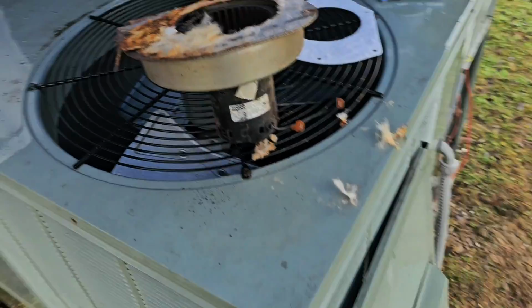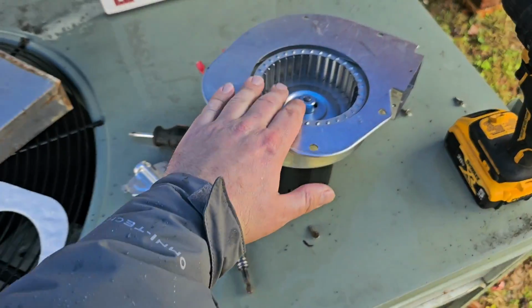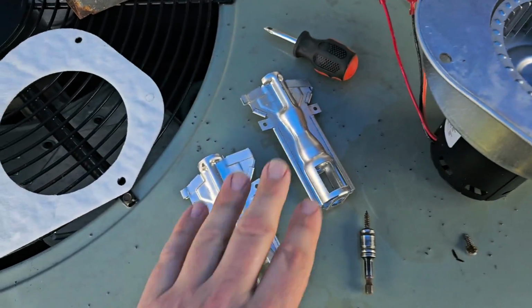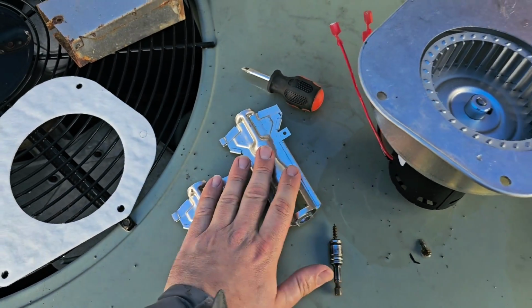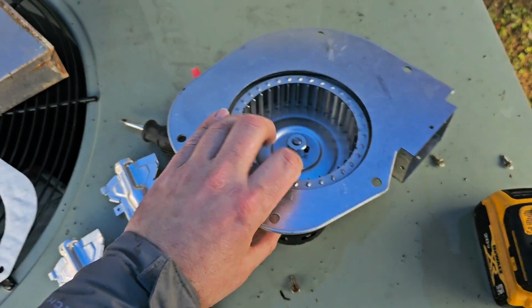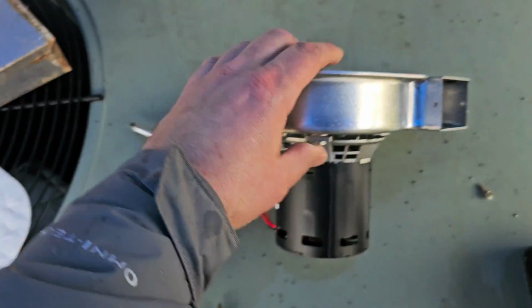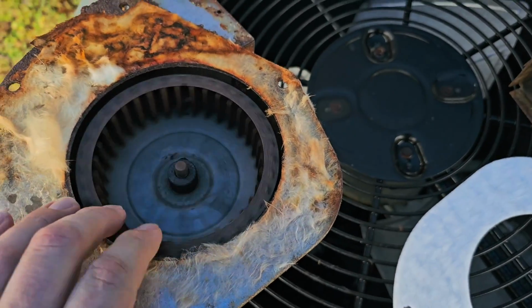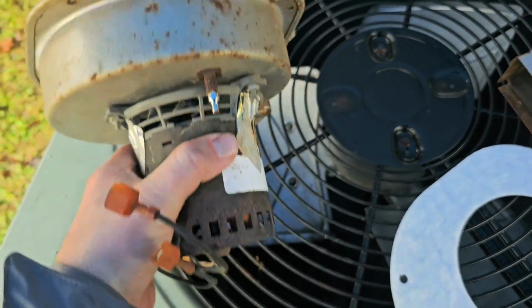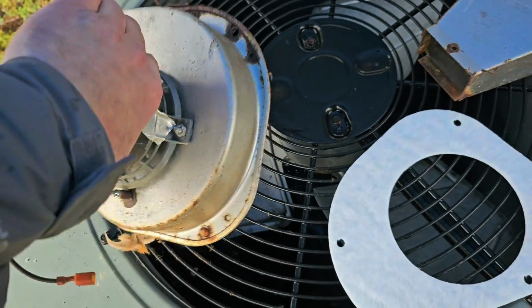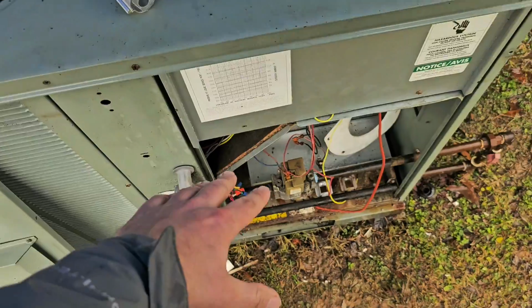Back on site, had to set up a tent because now it's raining. Let me show you what I got. Went ahead and ordered the inducer motor. So the inducer motor and the two burners that they didn't send me are in. I'm going to go ahead and put the new inducer motor on, and this is the old inducer motor, so you can see it's probably time for a replacement. Just want to make sure everything is new.